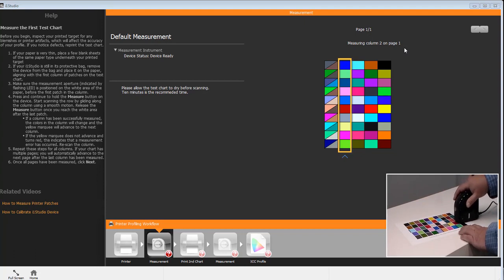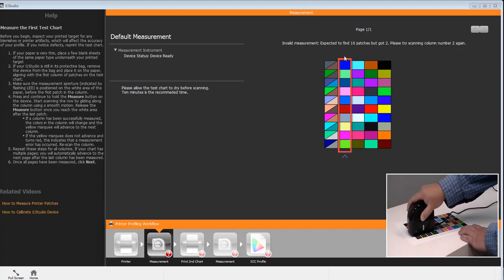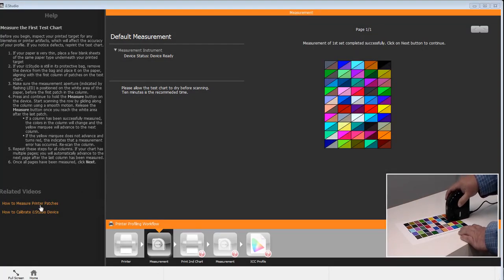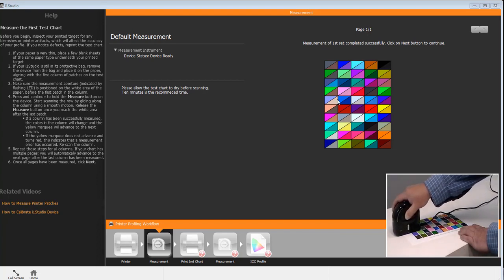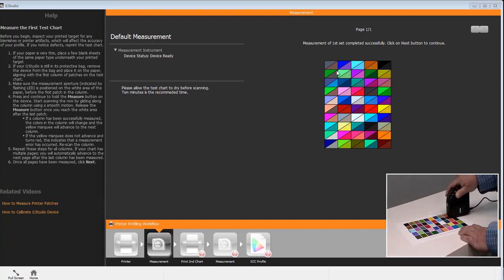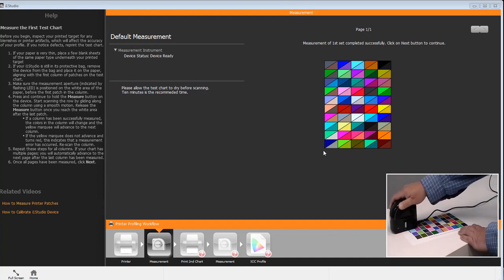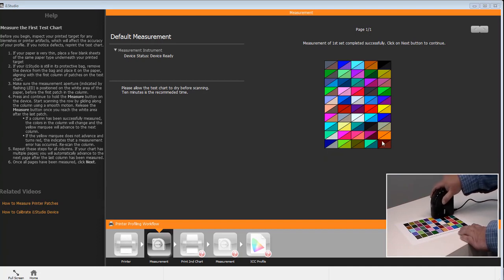If the measurements are not correct, you'll notice that you're going to get a red marquee around the patches, and it will prompt you to scan the column again. One thing to take note of as you're beginning the measurements on each row, you'll notice that the patches are going to show a diagonal line through them, showing you what was expected to be measured versus what was measured. This is a visual representation only and is not going to affect the outcome of your profile. So don't be concerned if your patches don't measure up correctly or look exactly the same.